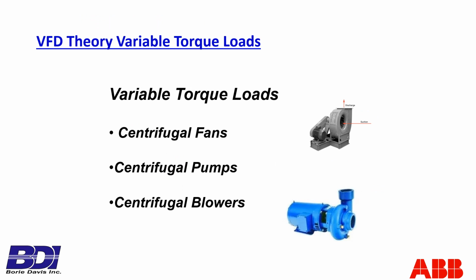All right, so now let's look at the variable torque load. That's our centrifugal fans, centrifugal pumps, and centrifugal blowers. These are the commercial HVAC market drive load considerations. This is the key. These are what we drive. We've proven that we can drive a constant torque load. Well, now the simplicity of the variable torque load surely says we can drive a variable torque load. And I hope you can grab that quickly from these next.